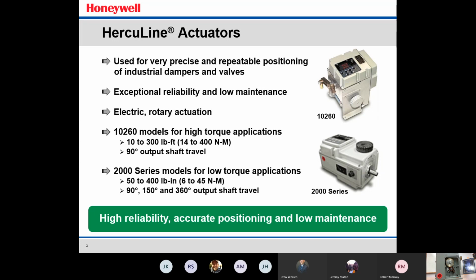The Series 2000 can go up to 400 inch-pounds. So it starts at 50 all the way up to 400 inch-pounds. And the output shaft travel can be adjusted from 90 degrees, 150 degrees, and there is also a special model, which is a 360-degree model. That particular actuator is used on a Surface Combustion integral quench furnace. If you get into some heat treat facilities that have Surface Combustion IQ furnaces, they had standardized on that 360 model a number of years ago, and you'll probably see these mounted up on the stack of the integral quench furnace. So there are other applications that use a 360 degree, but it's most widely used on the heat treat operations.